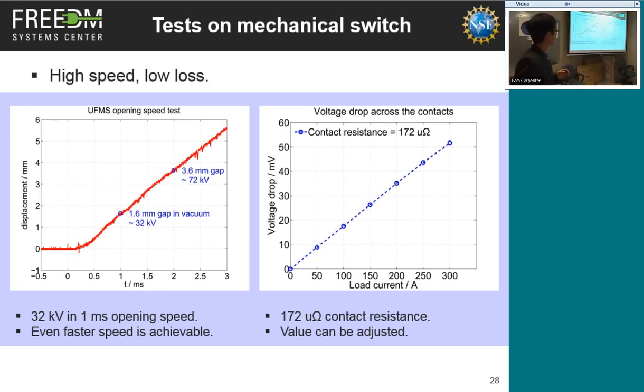We also calculated the voltage drop of the contacts when closed. We inject some current and measure the voltage drop at 300 amps—it's about 50 millivolts. We're talking about a millivolt at hundreds of amps, totally different from semiconductors. The contact resistance is about 172 micro-ohms, and we believe this value can be adjusted—and we did adjust it, bringing it down by adjusting the mechanical structure.